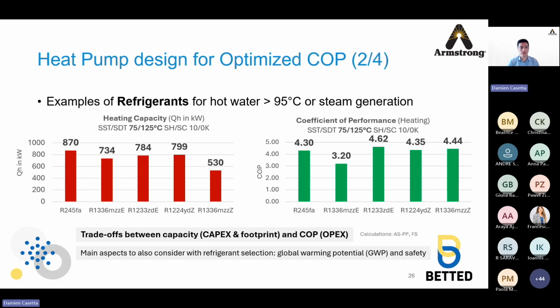However, you can see that for the same temperature conditions, they give you different heating capacity on the left and different coefficient of performance on the right. High heating capacity means more compact heat pumps, so less capex, less footprint. High COP means less electricity, then less OPEX. So selecting the right refrigerant is basically a trade-off between these. Additionally, the main aspects to consider are environmental aspects, global warming potential primarily, and safety efforts that come with the use of those refrigerants in heat pumps, and to make them applicable in a real manufacturing environment.